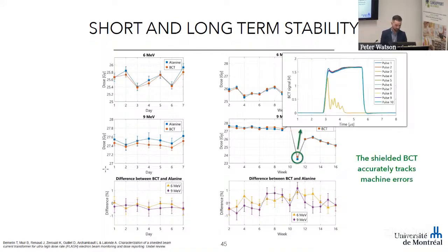The other thing that is worth mentioning is that for 1 day, we actually were lucky. The Mobetron is very stable, but every now and then it can happen that a pulse is not emitted properly, and this happened on week 11. We see here that the third pulse actually had an odd shape. It was just partially emitted. And what's interesting is that if you take the integral of this signal and account for it, and compare it to the dose measured by the alanine for this irradiation, we're still within 1%. That's very reassuring, because the machine can have issues, but as long as you track them properly, it's a good sign. So that was also a very positive result.